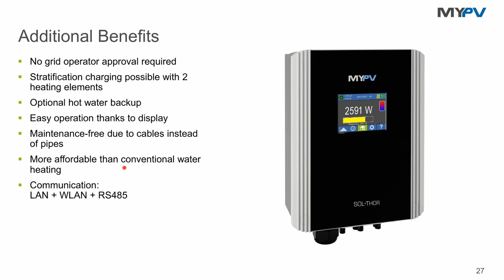Technical details: power range from 0 to 3.6 kilowatt theoretically, depends on the heating element, so you can use smaller immersion heaters as well. The DC input voltage is between 30 and 230 volts, so 1 up to 10 panels is possible, but for 10 panels we're talking about 2 times 5 panels in parallel, otherwise we would exceed the top level of the voltage. The input current is limited to 26 amps - more current, if available from the panels, would not harm the Sol-Thor. Only too much voltage can harm the device, so please always consider that.